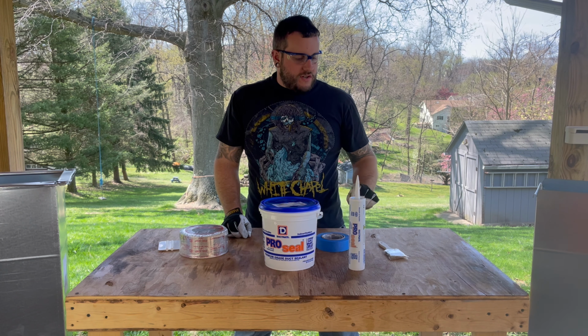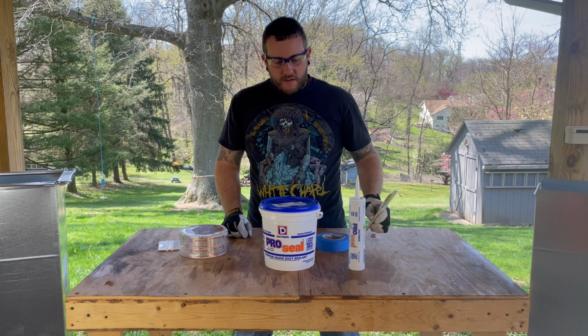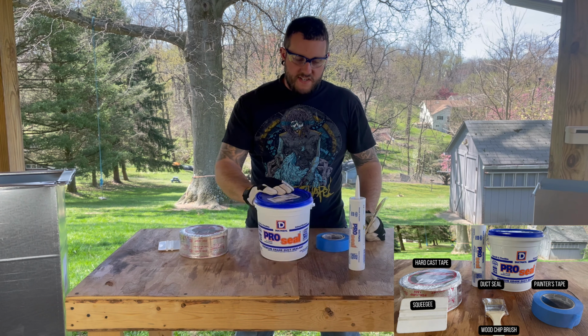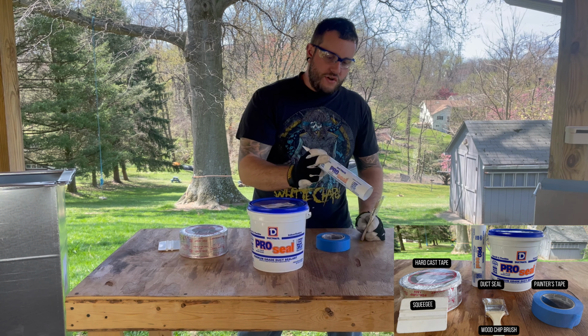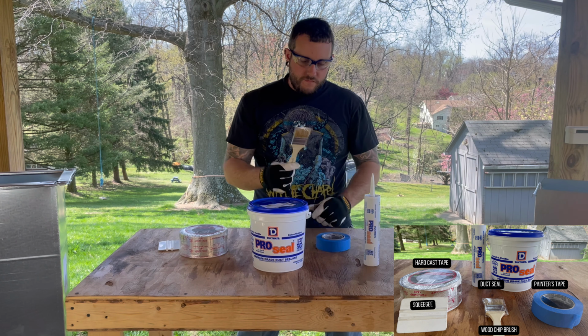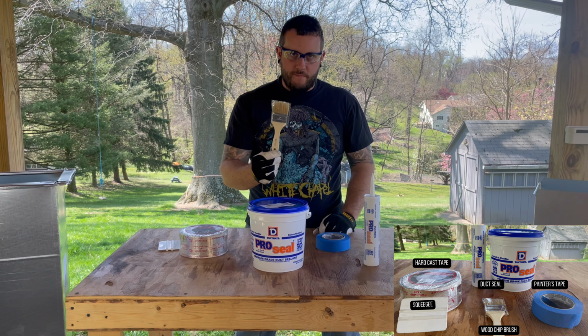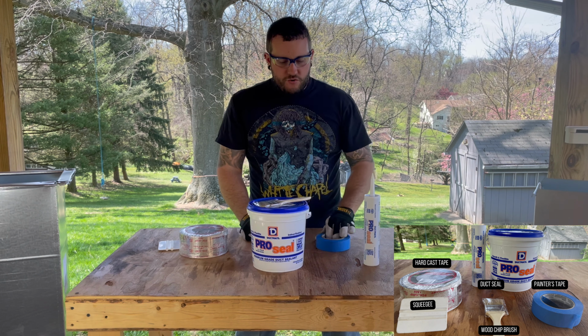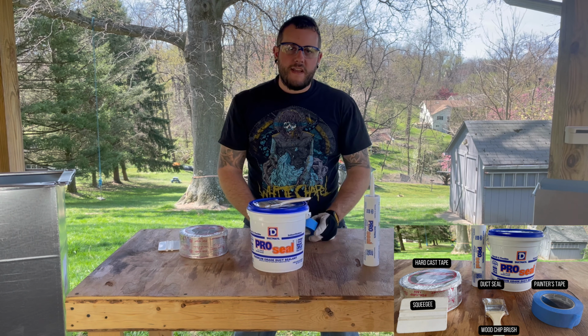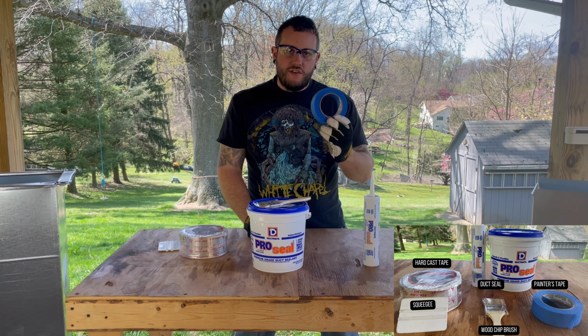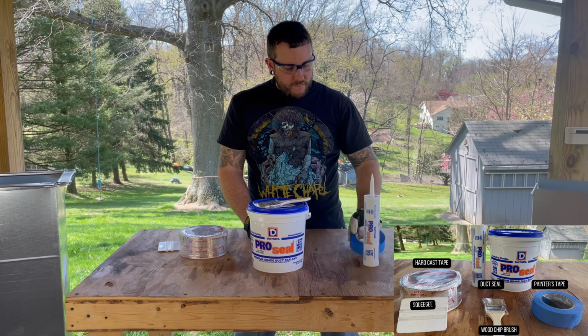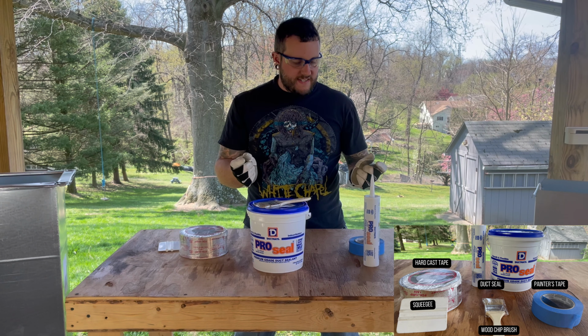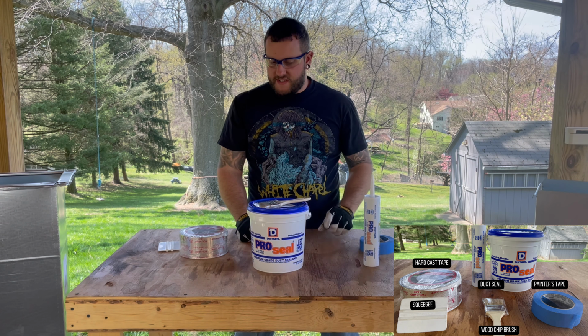So the first thing we want to do is go over some of the tools. The duct seal comes in either 1 gallon tubs, or you can get it in little caulk tubes. We're going to paint it on with just a wood chip brush. If you're doing exposed ductwork and you need to make your duct seal look really nice, you can use painter's tape to give you a nice line of the duct seal around the joints.